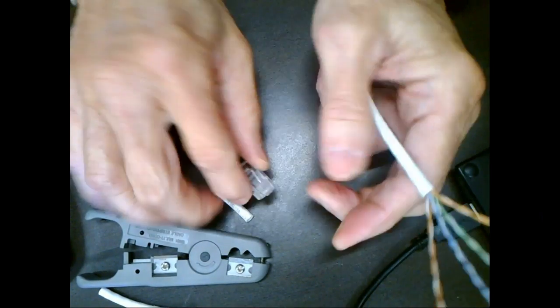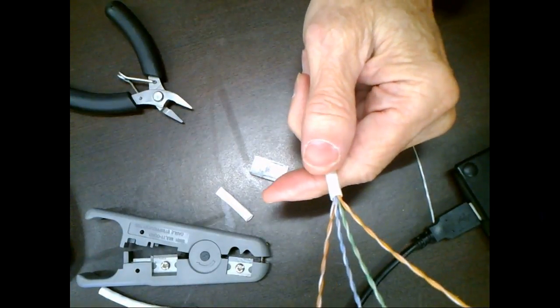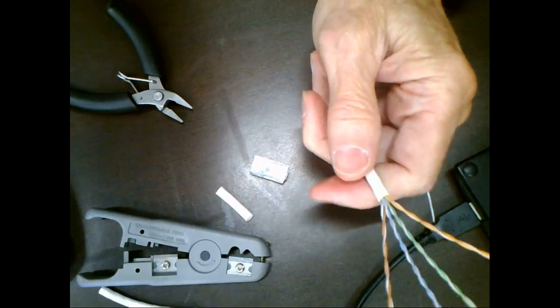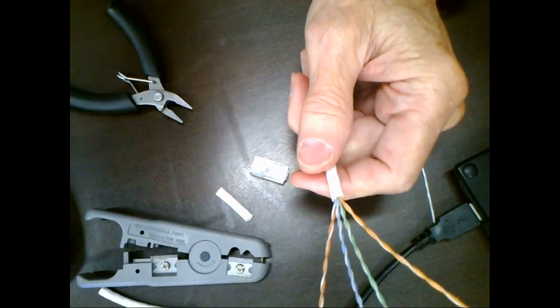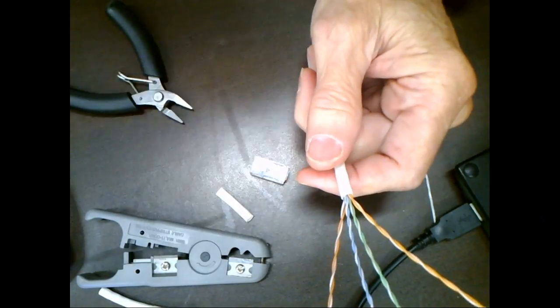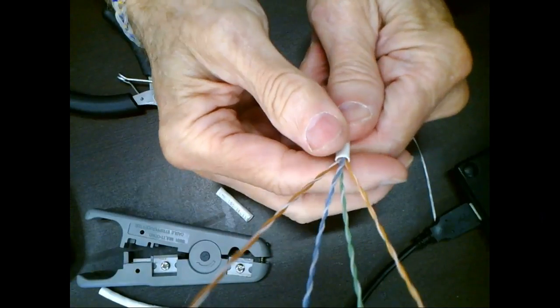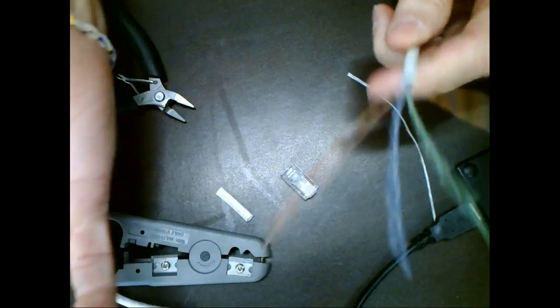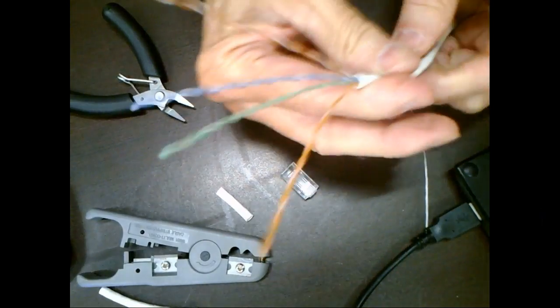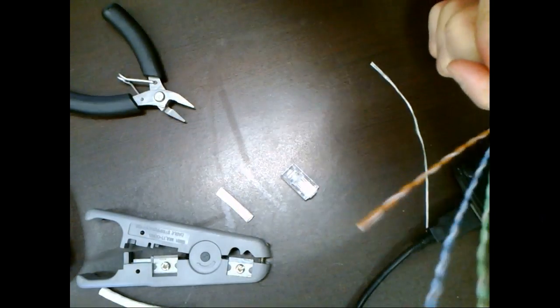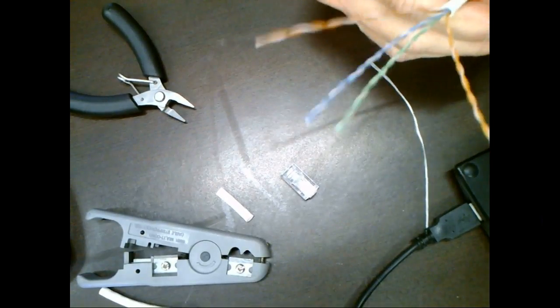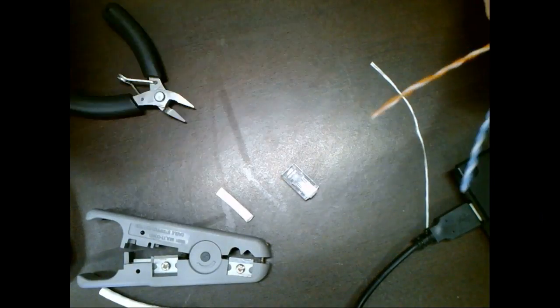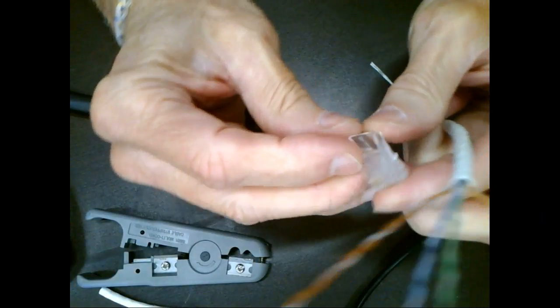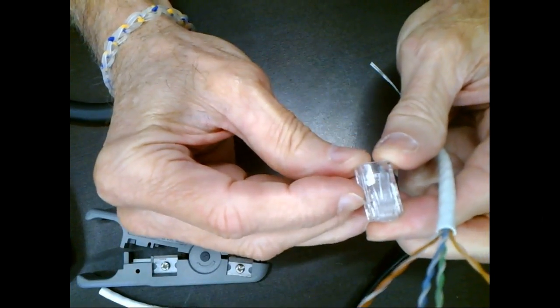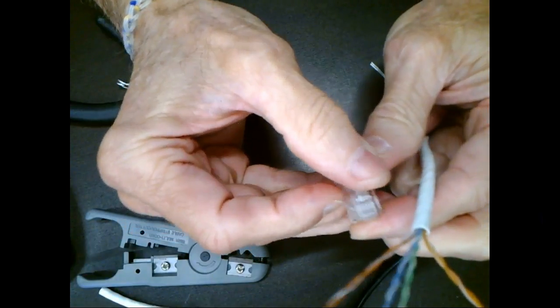And then if you ever look at an industrial switch, an industrial Ethernet switch, it'll have a metal ring around the outside to make up that shield when you plug it in. We're not going to use STP cable. We're going to use UTP cable because we're not in an environment here that needs that. But those green cables that y'all have that are so long, those are STP cables. So next time you get them, look at the connector, and you'll see the metal shield runs down to where it actually plugs into the RJ45 jack.